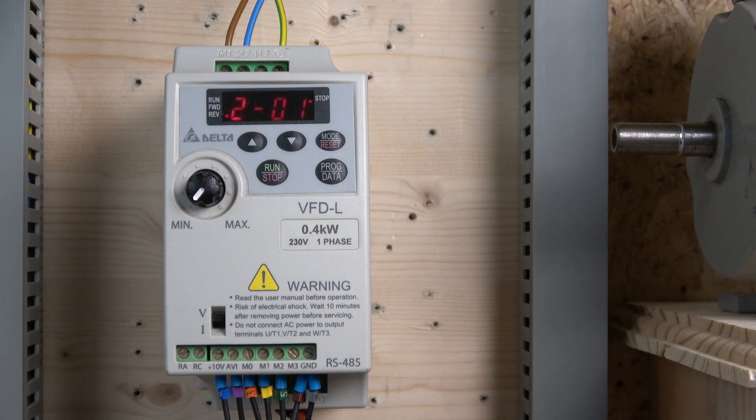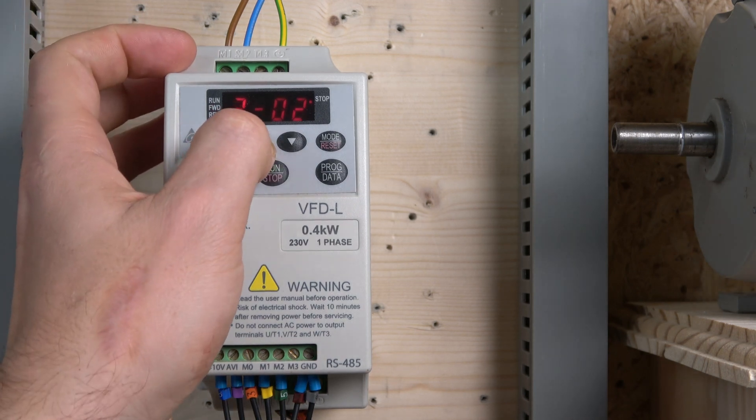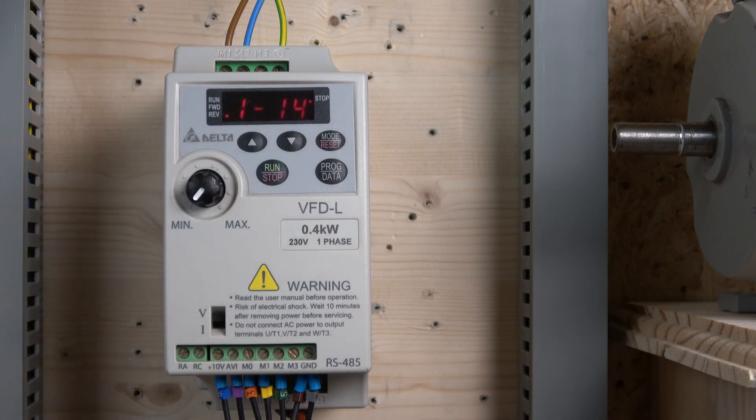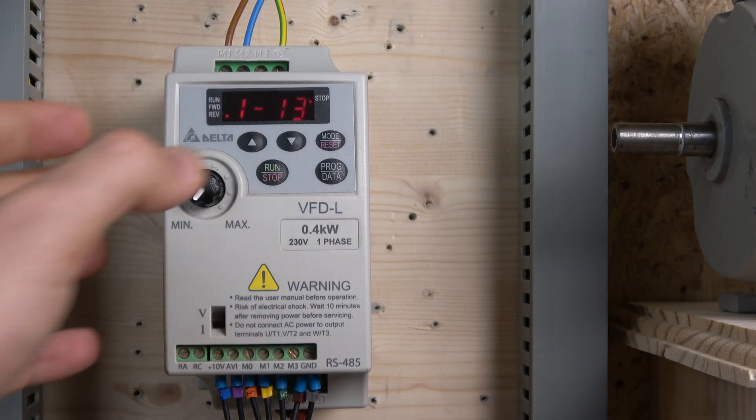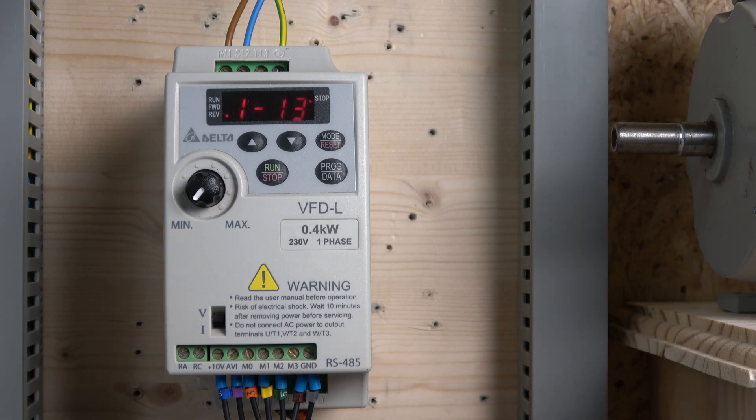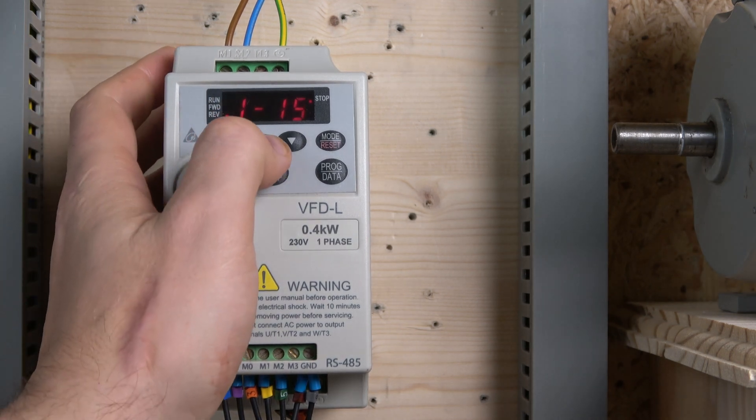From there on we need to set up our acceleration for jog and actual jog. That is going to be in parameter 1-13 and 1-14, that's going to be deceleration and acceleration. And obviously if you want to change your jog frequency, it is in 1-15. I believe it's standing at six hertz.